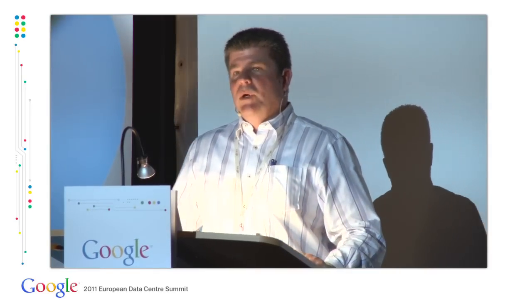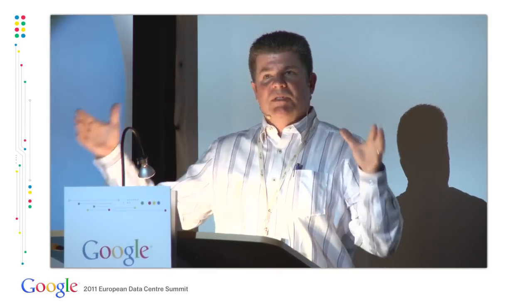Hi, very interested to know what happened to the humidity after you turned off the dehum and you opened the window. Sure. So these networking rooms are in larger buildings, and the buildings themselves are actually pretty well sealed. And the makeup air is handled at a common air handling unit. So allowing the humidity to go from 20 to 80% relative humidity, using the full expanded ASHRAE operating range, we found that we didn't need to do local humidification control, that the air handling makeup air units were sufficient.